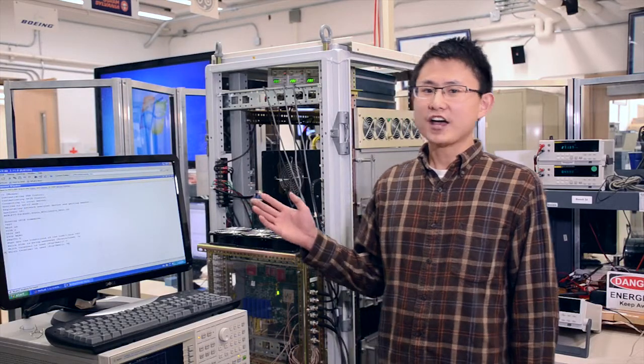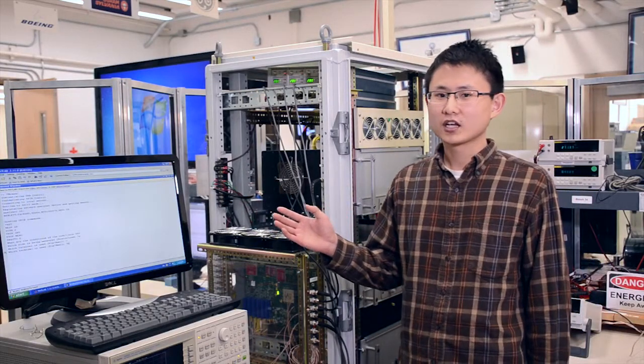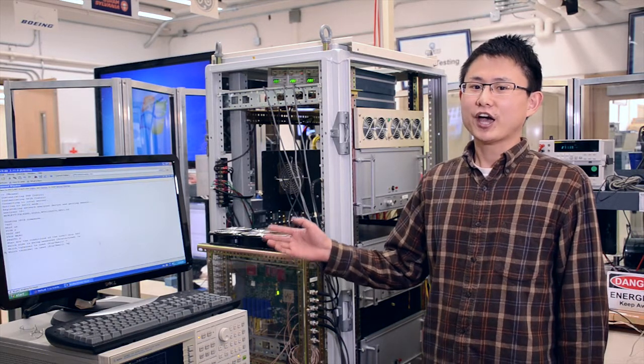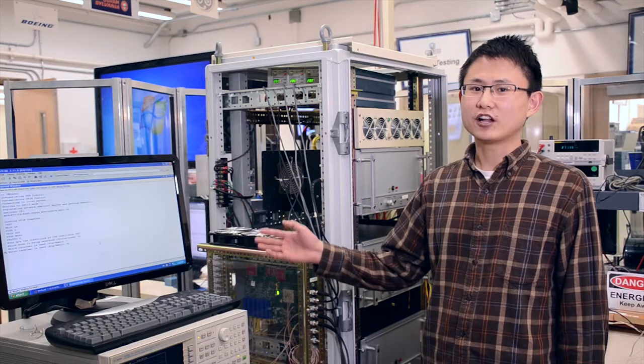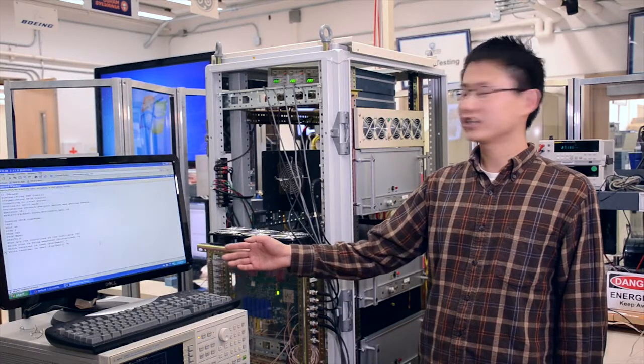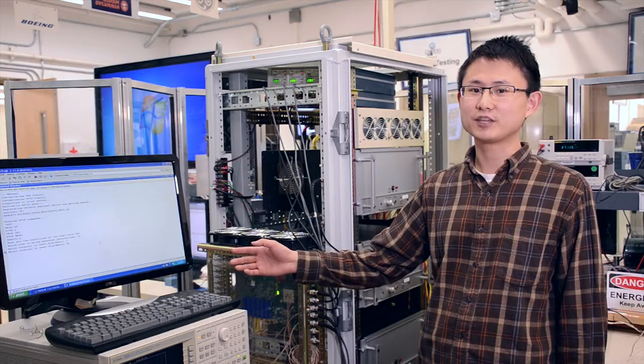Here is our DQ impedance tester. To measure the impedance, I just use the PC and the user interface running in the PC to measure the impedance automatically. Here I already input the command, the measurement AC to measure AC impedance. Once we get the output impedance of VSI and the input impedance of the rectifier, we can plot a generalized Nyquist plot, and it can predict the system stability condition correctly.